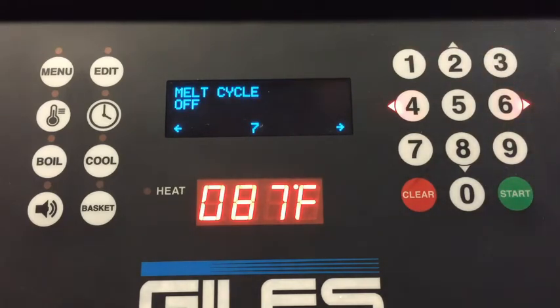Melt cycle off. The melt cycle you would use if you were using lard or sometimes some very heavy oils. We've had to turn it on to keep from getting alarms on that fourth probe, because it brings the temperature up a little bit slower and you've got oil movement. You won't get that fourth probe error first thing in the morning. That'll run until the temperature gets up to 270 degrees. After 270 degrees, it drops out of melt cycle and goes into normal heating mode.